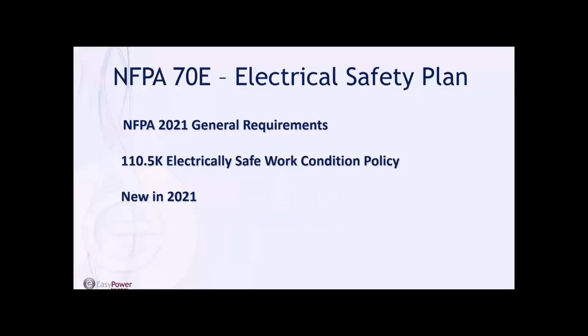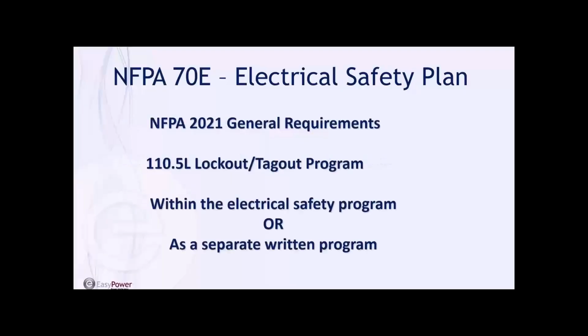To resolve, recommend, and implement changes so a similar incident is no longer reported in the future. New in 2021 was the electrically safe work condition policy or practice. Many times a facility might say we're going to allow our maintenance team to work on all devices within the electrical distribution system up to, say, an 8-calorie level, and anything beyond that we're going to rely on our licensed and experienced electrical contractors to do the work at hand. That type of statement is really indicative of this new requirement in the safety plan.